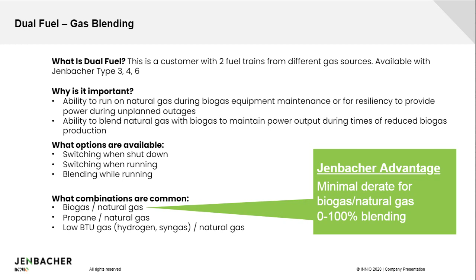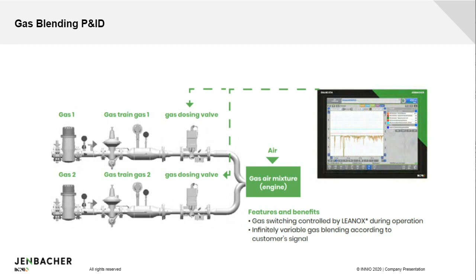So really you have often a very similar output on both gases, which obviously is what you would desire to have. So if we now look at the two gas supply trains, this is just a schematic how it looks. So basically, obviously you had to have your biogas supply train and your natural gas supply train, and both would come together at the gas air mixture valve there, where you add the air to it for the combustion process. And our controller, the DIA.NE, would then handle the blending and the dosing of those two gases. And basically you could set any variable blend of the two or do a switch between one and the other.